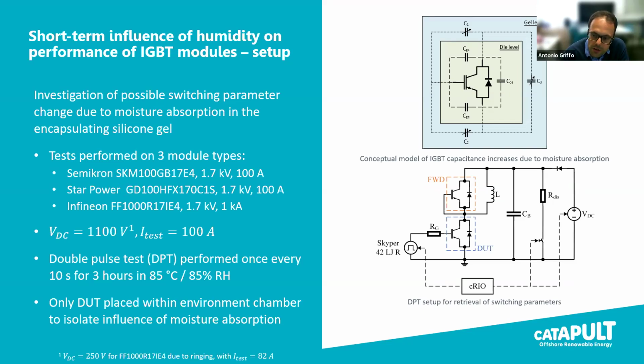Due to this variation of the equivalent capacitance of the silicone gel, we were interested in understanding what could be the implication in terms of switching characteristics of the power devices. That's where this test setup, which represents a standard double pulse test, was conducted on a series of devices typically used in wind converters. Next, please.